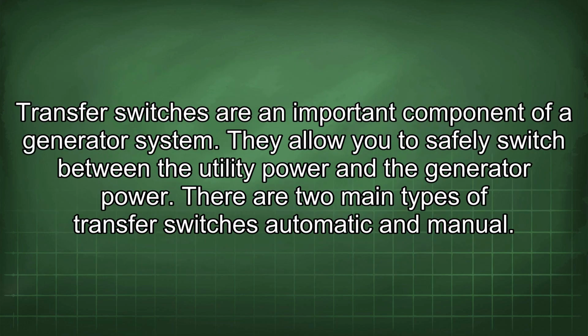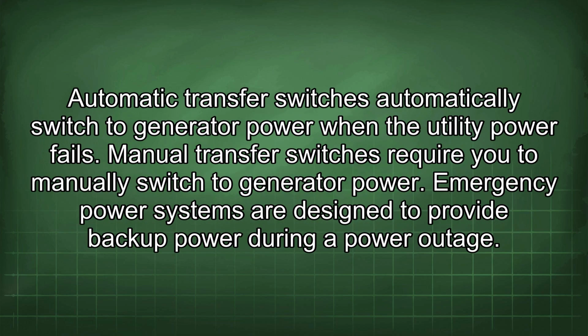Transfer switches are an important component of a generator system. They allow you to safely switch between the utility power and the generator power. There are two main types of transfer switches: automatic and manual. Automatic transfer switches automatically switch to generator power when the utility power fails. Manual transfer switches require you to manually switch to generator power.